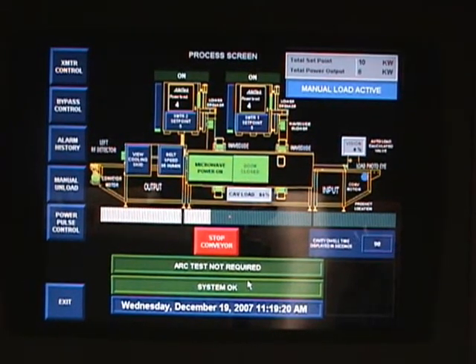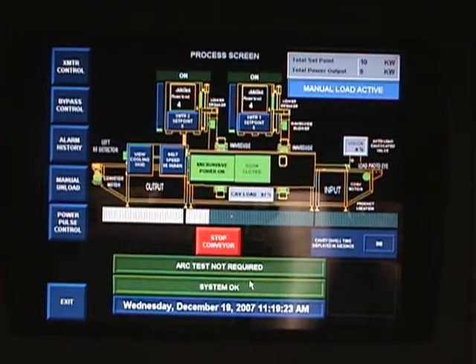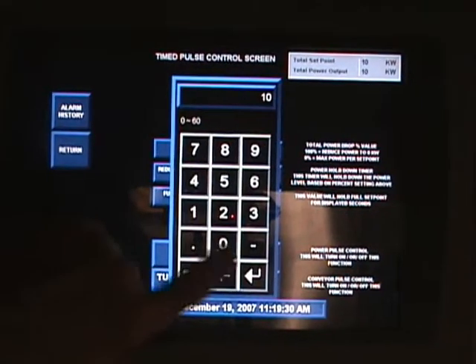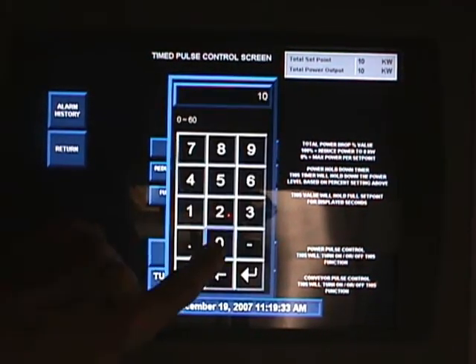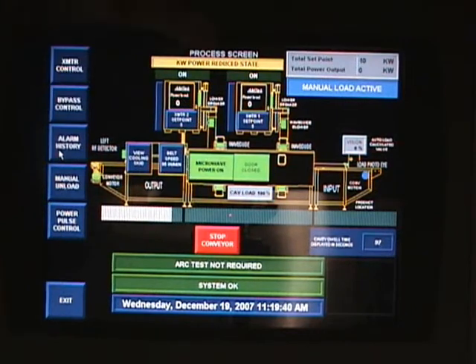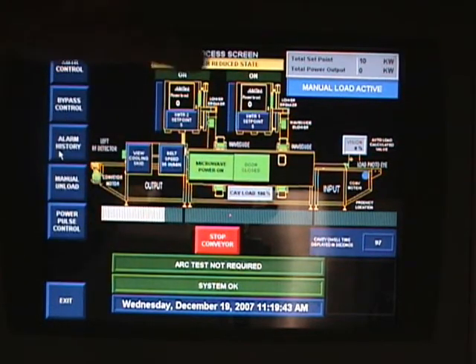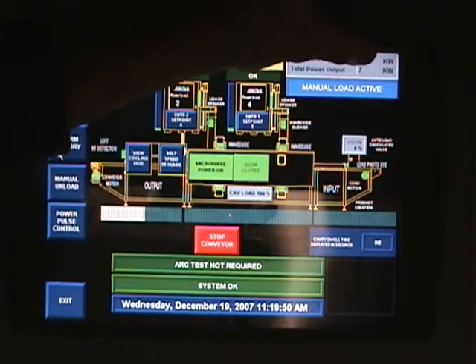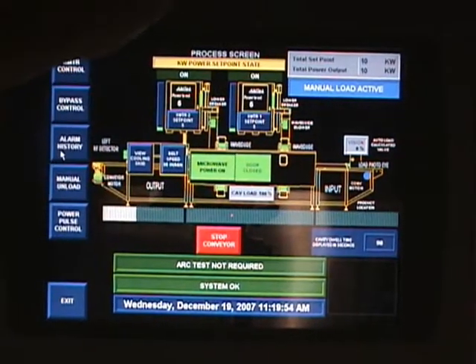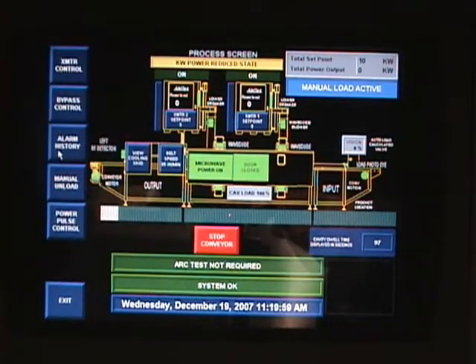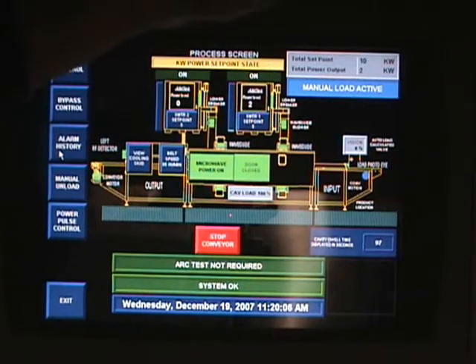Let's go to pulse power. I'm going to turn it on and change this to ten and ten. You'll see the pulse is active — now it's in reduced state and goes to zero. Even though the oven's still running, I did not pulse the conveyor. Now pulse power is on and it's powering up during the ten seconds of run time. In ten seconds it's gone back down — it's in the hold period, pulsing off and on at zero to ten kilowatts. That can be changed to five or two or whatever you want.